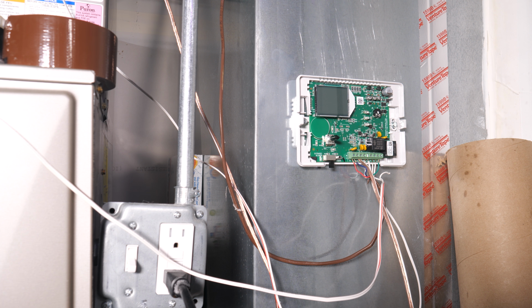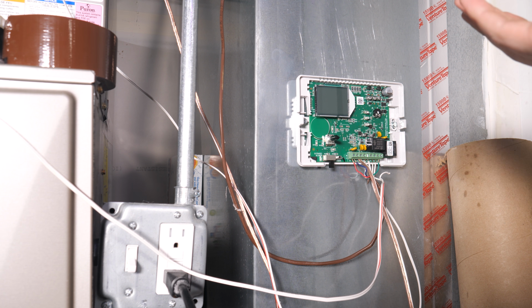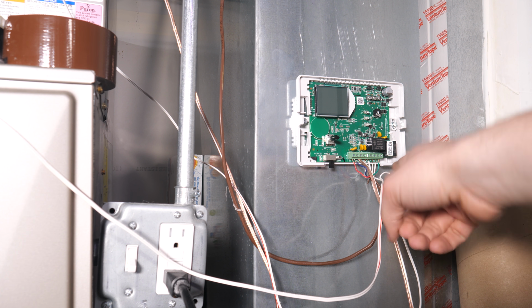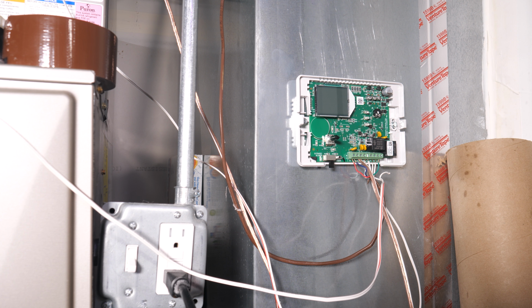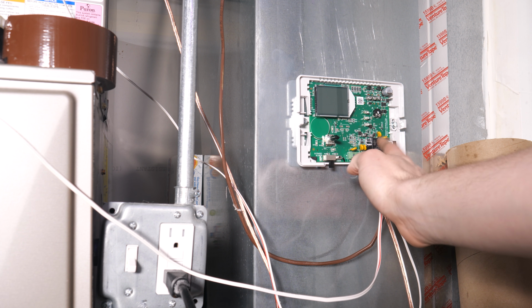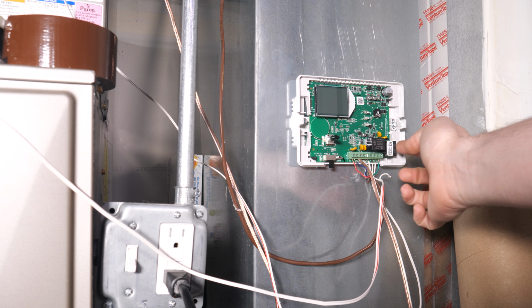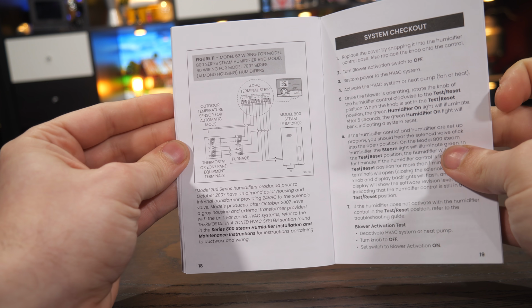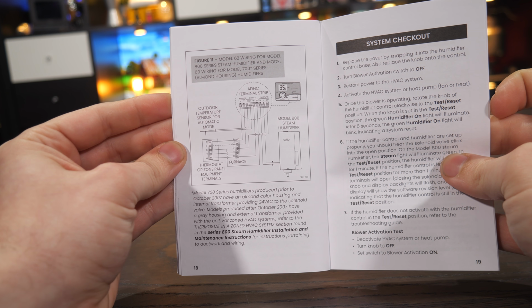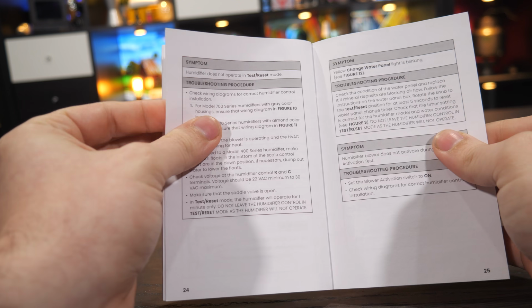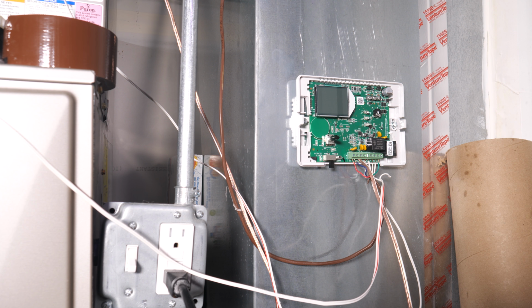Now, why on earth does Aprilaire choose to distinguish them in this way? I don't know, but it's really frustrating, and they clearly don't want people figuring out how to wire this digital version to the manual one because they just don't even tell you it's possible. But it's totally possible. This is just a relay. One of these relays does the humidifier, the other relay forces the furnace fan on, but they do not give you a wiring diagram for how to use this with the manual model, even though it's completely possible. I've been meaning to make a video on right to repair for a while. This isn't quite part of that, but man, this is dumb.